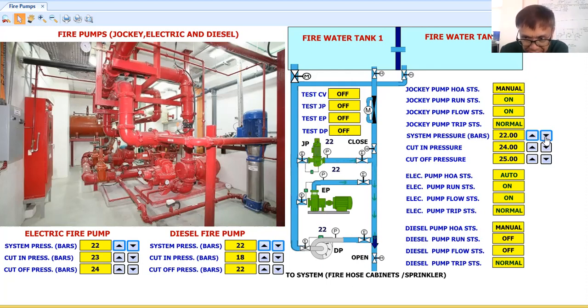Now, if I still have a big pressure drop here, okay, then my diesel pump will try to help, okay? So this is how these fire pumps will work, okay? So let me simulate, okay? Guys, this simulation is just to give you an idea how these pumps will kick in. In the event of a small water leak, the jockey pump will handle it. Now, if there is a big pressure drop, 1 bar below the cut-in pressure of the jockey pump, then your electric pump will run.